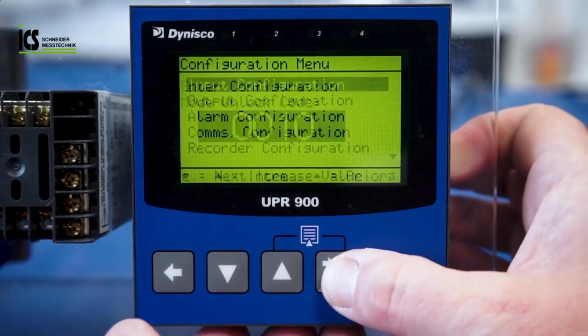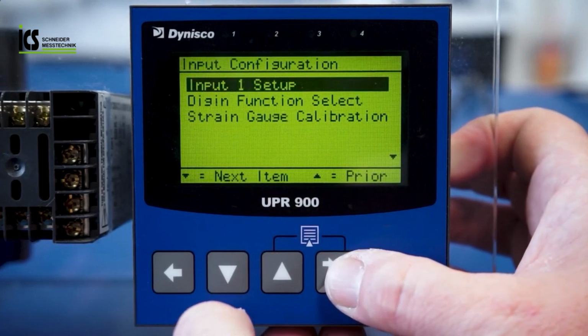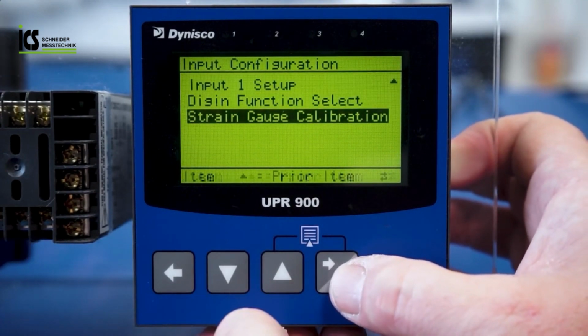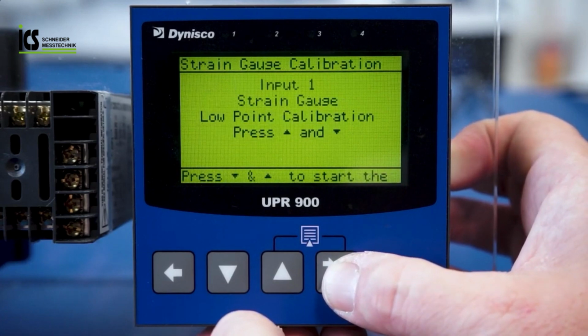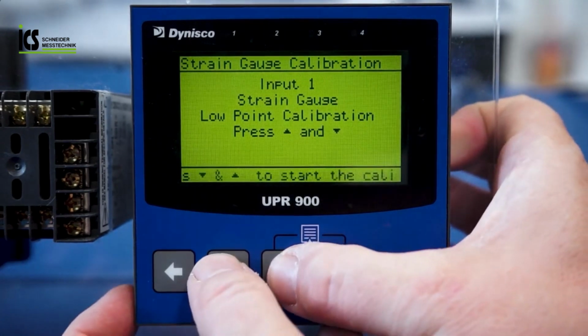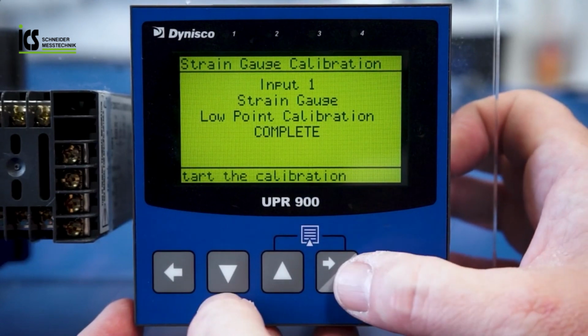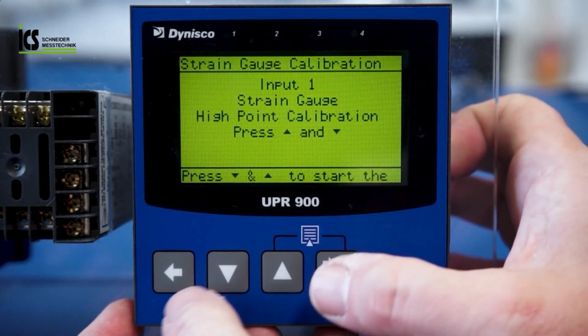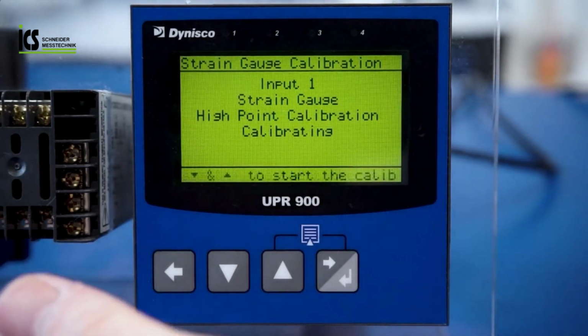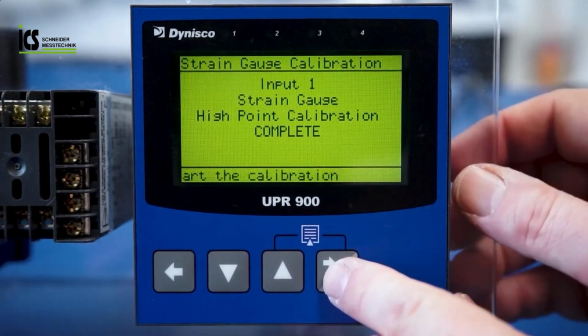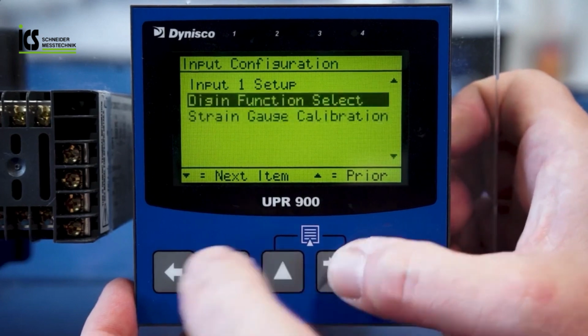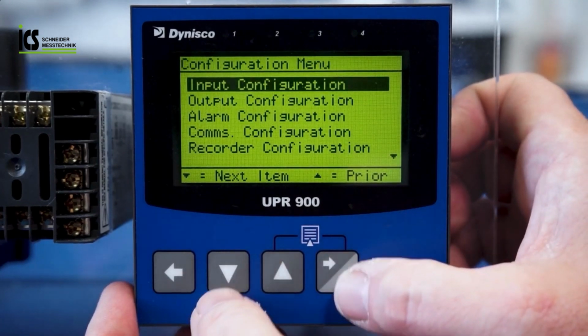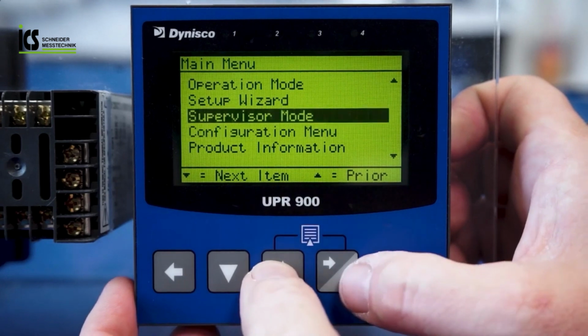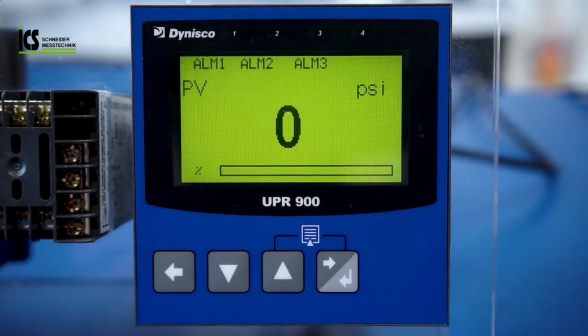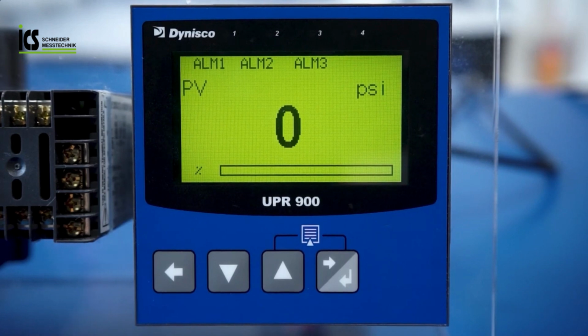Once in the configuration menu, the input configuration is selected to find strain gauge calibration. The instrument prompts the technician to test the high and low calibration points via the up and down arrow keys as demonstrated. Once the high and low points have been tested, the indication device will show calibration complete. With the sensor and instrument calibrated, the technician can then exit the configuration menu and then select operation mode. Dynisco recommends this step be repeated anytime the sensor exhibits pressure readings that appear abnormal or if the sensor has been swapped out.